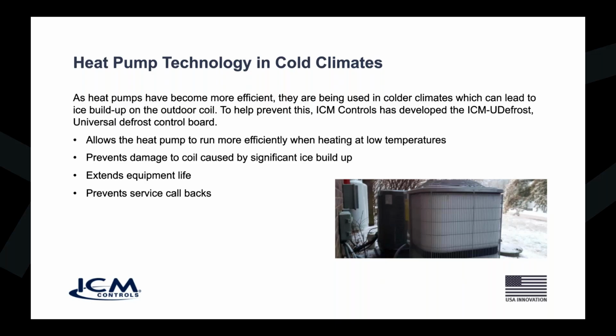But to do that, they have to have a piece of equipment inside there to prevent ice buildup. You can see from this example, the coil has frost all over the front of it there. And the coil is what you see on the outside of that big box there. That's in your heat pump. You're going to want to push air past that coil and get rid of that heat. But the problem is you can't.